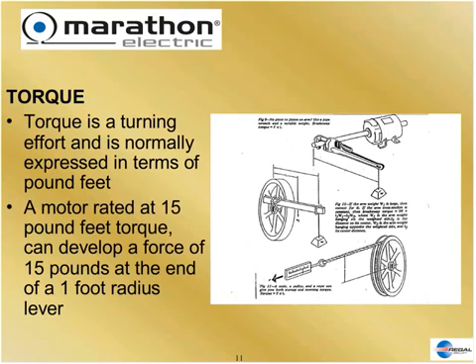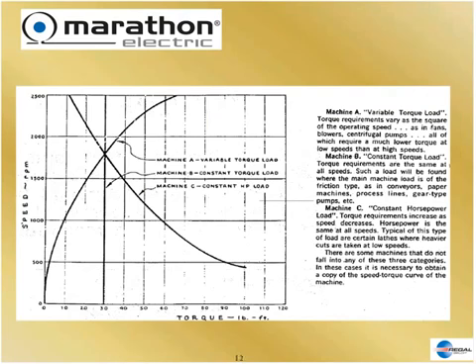Slip creates torque, and it requires torque. Before we talk about motor torque, there are basically three kinds of classic machines. Machine C is not as common, so we'll concentrate on the first two. Machine A is a variable torque load — as you can see by the chart, torque increases exponentially as speed increases. That's why it's called a variable torque load.